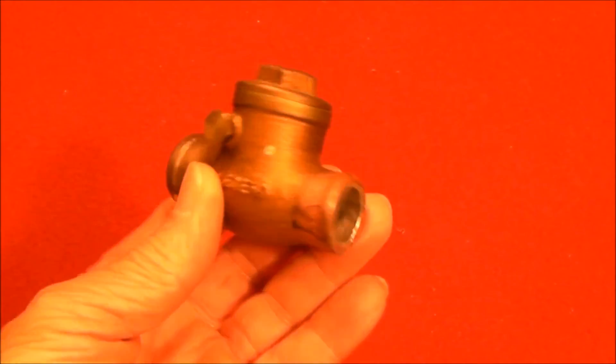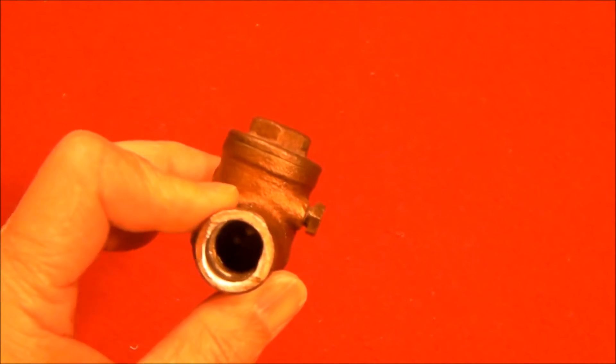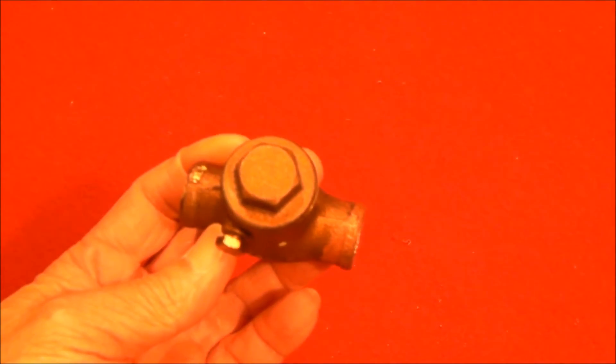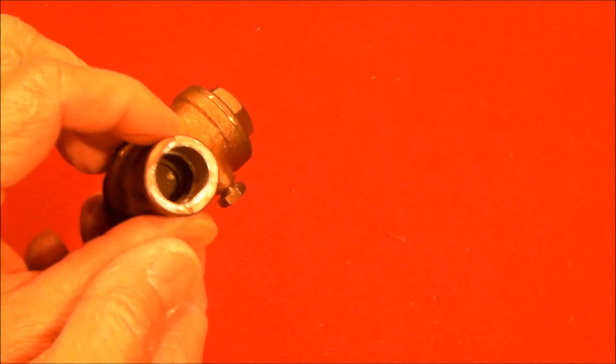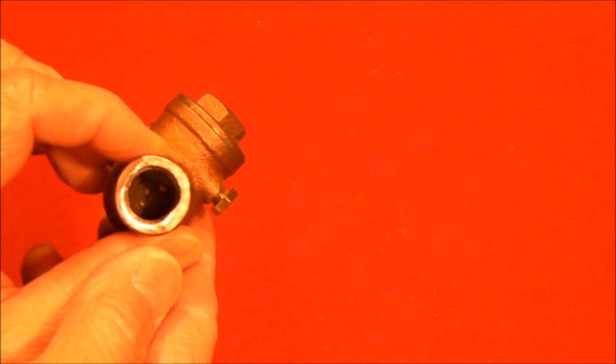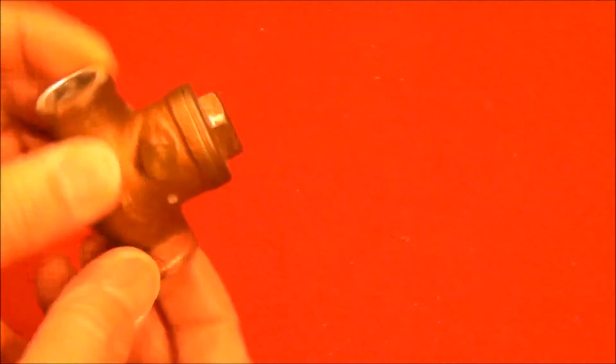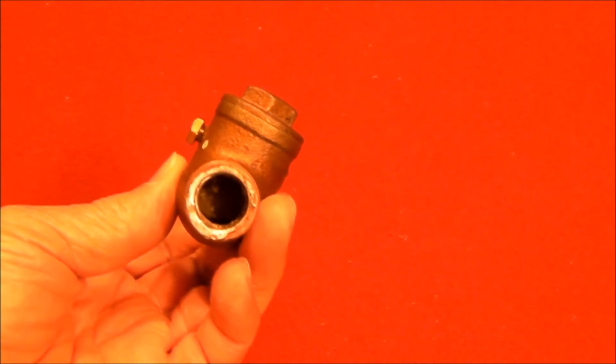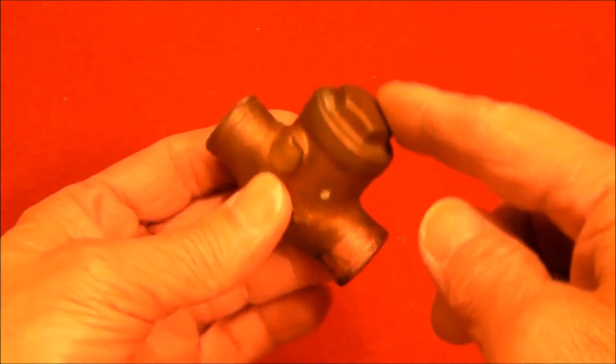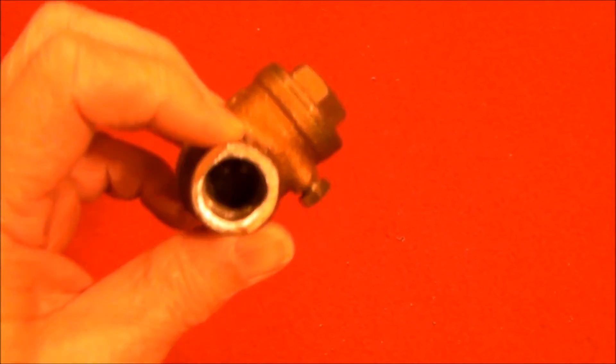I have the check valve out of the system and it's definitely stuck partially open. I can't move the flapper from either side. You can't really see very well down in there, but it's jammed in a partially open position. I'm going to try to get it apart and we'll take a look and see what's going on.